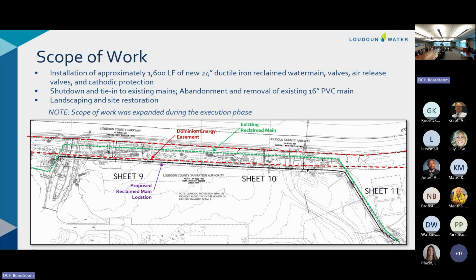Sure. Over time, based on our experience and what we've learned, on the water side all of the pipes are ductile — we only use ductile for a high pressure system. On reclaimed, in the past we used PVC, but over time we've learned that when you have higher pressure, ductile iron, while slightly more expensive upfront, offers better life and the ability to handle higher pressure. That slightly increased premium makes a lot more sense — you get more out of ductile iron pipe than PVC, a better return on investment.